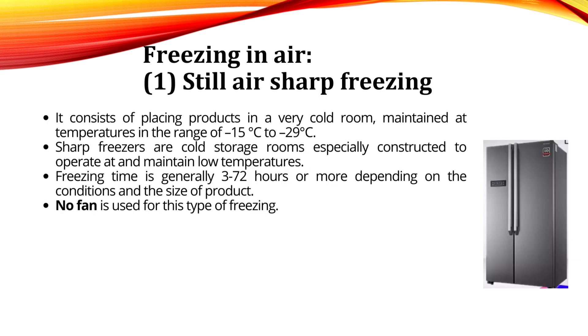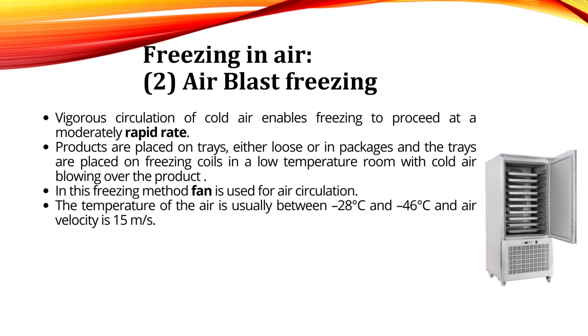Still air sharp freezing uses cold rooms specially constructed to maintain temperatures at minus 15 to minus 29°C, with freezing times of 3 minutes to 72 hours depending on conditions and product size. Air blast freezing uses vigorous circulation of cold air to enable freezing at a rapid rate; products are placed on trays with cold air blown over them using a fan, at temperatures between minus 28 and minus 46°C and an air velocity of 15 meters per second.